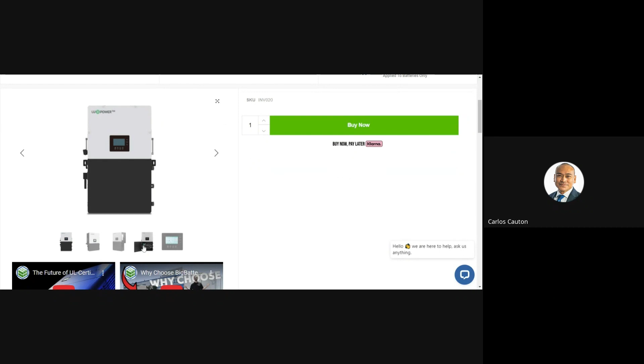But what I like most about this inverter is that it's both AC and DC coupled. You can literally, if you have strings already on the roof, whether it's Enphase or Solar Edge, you don't have to change the string configuration. You don't have to mess with any of the series on the roof. You're just going to bring that voltage down, or your strings down, and into the AC port. It's awesome. So you can take any high voltage solar PVs on the roof, take it away from the sub panel, and bring it in as AC.